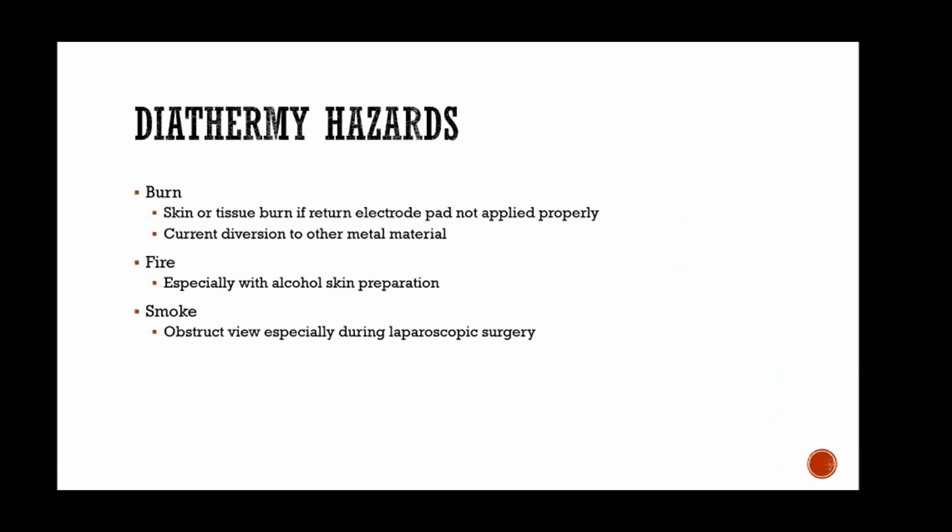So, the possible diathermy hazards. You can have a burn, either skin or tissue burn, if the return electrode pad is not applied properly. And also current diversion to other metal material.